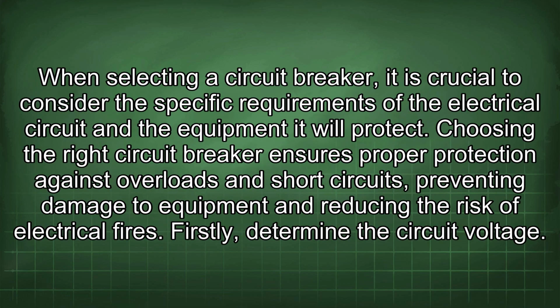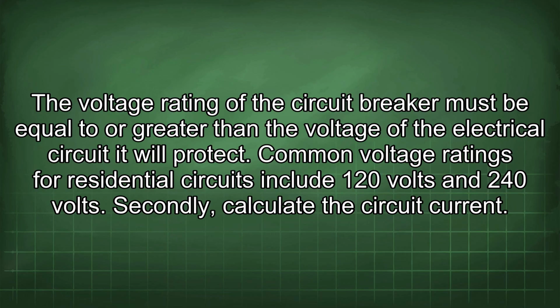When selecting a circuit breaker, it is crucial to consider the specific requirements of the electrical circuit and the equipment it will protect. Choosing the right circuit breaker ensures proper protection against overloads and short circuits, preventing damage to equipment and reducing the risk of electrical fires. Firstly, determine the circuit voltage. The voltage rating of the circuit breaker must be equal to or greater than the voltage of the electrical circuit it will protect. Common voltage ratings for residential circuits include 120 volts and 240 volts.